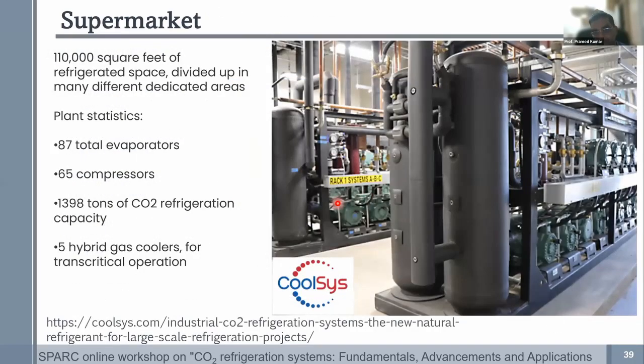These are some of the examples of what CO2 systems typically allow you to have: very clean rooms, workrooms or floor spaces where you can have rack mounted systems with multiple compressors. All of them can produce very large tonnage, of the order of 3 to 5 megawatt of cooling, with very compact CO2 systems, and that is where the beauty of the system actually lies.